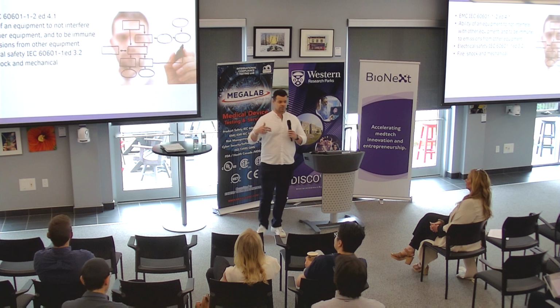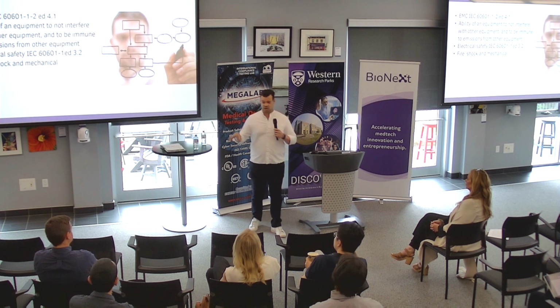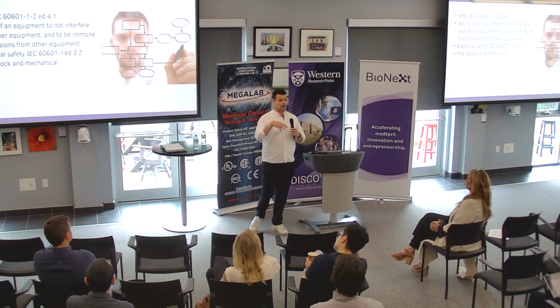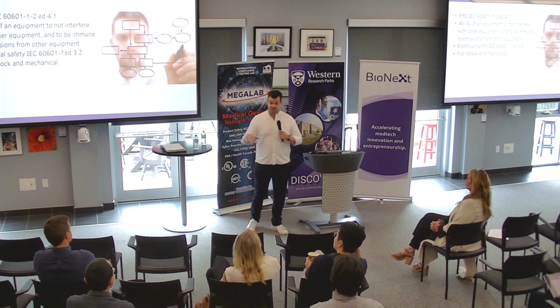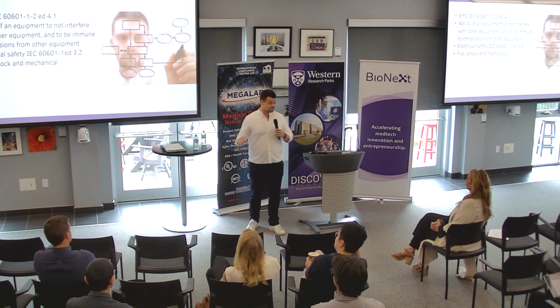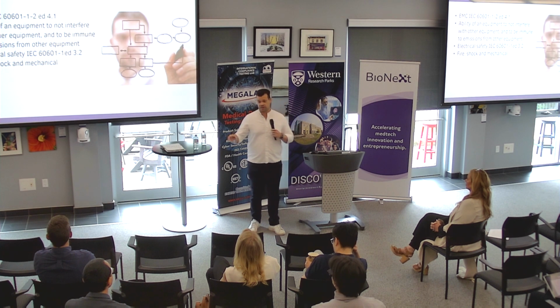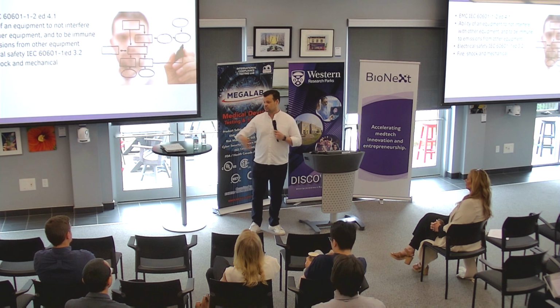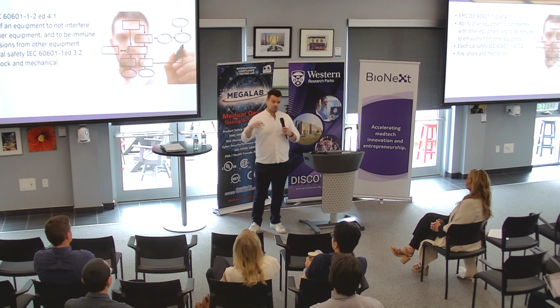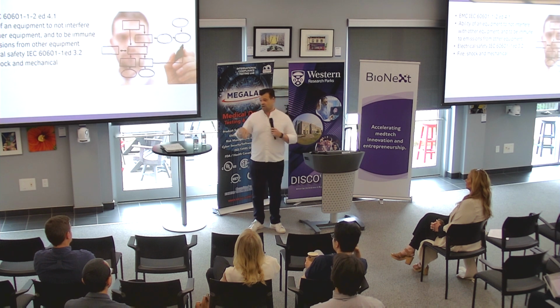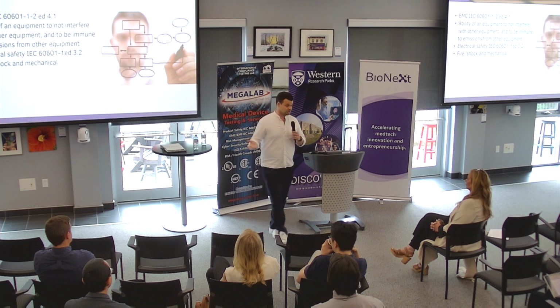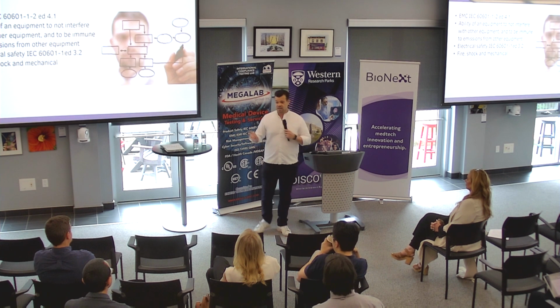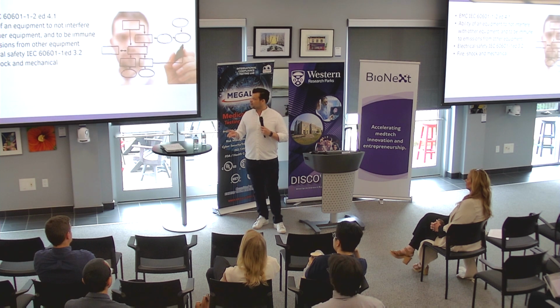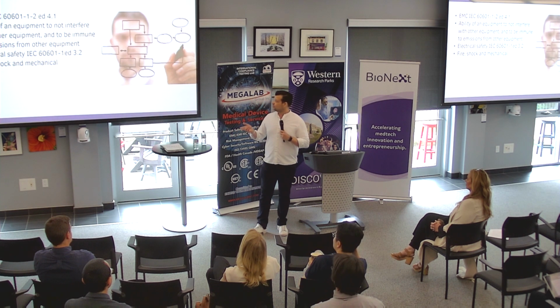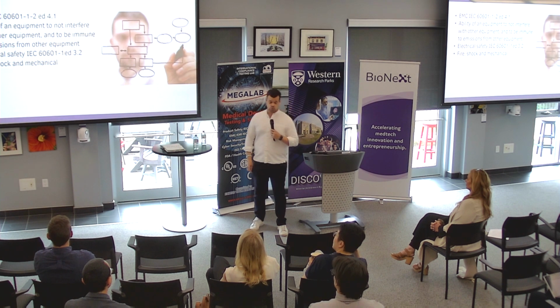And in the medical device field, if you think about being in an emergency room with all that sensitive equipment, you also don't want other equipment to interfere with your device. So that could be a minor inconvenience, right? In some cases, this is flickering, or the hospital bed won't go up and down because somebody's walking by with a radio. Or it could be really serious. Somebody's walking by with the radio, the ventilator stops working because there's too much EMI noise, right? So that's why in the medical field, it's a lot stricter than other fields. Now, the other one that you'll see down there is electrical safety, IEC 60601-1.